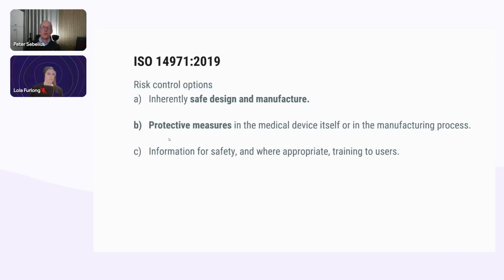And secondly, if you change the design of the medical device to reduce the risk, that does not automatically mean that you are going with this first option, inherently safe design and manufacture. A lot of people get this wrong. I say that if you apply a protective measure, let's say an alarm or a cover, it is a protective measure, right? A cover or an alarm, they are protective measures. They are also changes to the design. I would even argue that if you put a sticker on the product, that's information for safety, like don't touch or do this before you use it. That's also a change to the design.